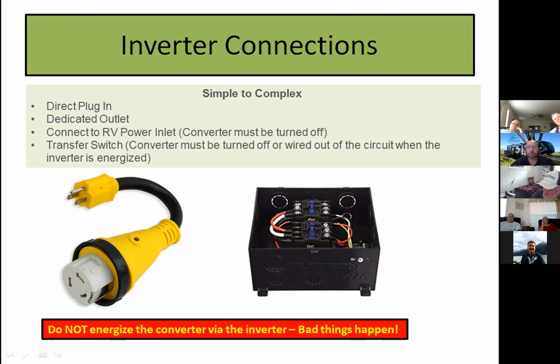If you don't do that, the converter will be trying to stuff power back into the batteries while the inverter is pulling it out. It'll get into a vicious cycle and run your batteries down very quickly. It's not a good thing to do, so make sure you're on top of that.